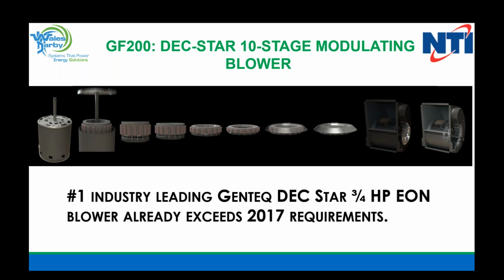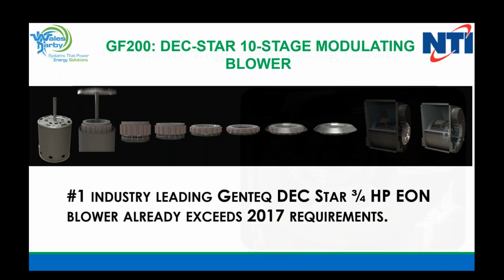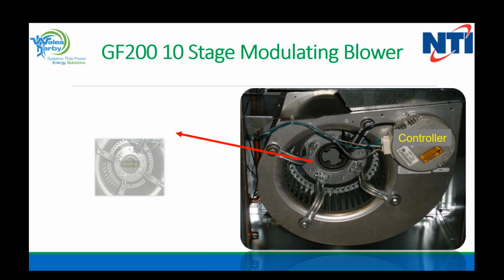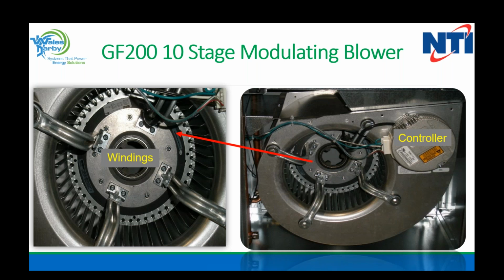Okay, this is the steps of putting the motor together. So it's a bunch of windings, and we basically run a wire to those windings, and we'll pulse the windings as need be. So this is where your blower motor would normally be mounted, right into the center. But what we have instead is a controller that mounts to the blower housing, the actual housing of the blower. And then you've got your 4 arms that go in, that's holding the magnet, and then will pulse the magnets, and the wheel will actually rotate around that. So much different than anything you've ever seen.